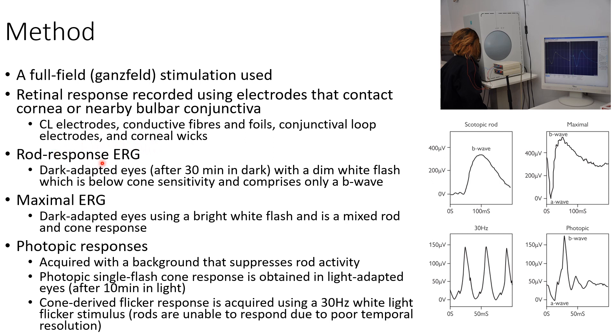Rod response ERG, that is scotopic ERG, is recorded in dark-adapted eyes after 30 minutes in the dark, with a dim white flash which is below cone sensitivity, and comprises only a B wave, as you can see in this picture. Maximal ERG is recorded in dark-adapted eyes using a bright white flash and is a mixed rod and cone response, as you can see in this picture.